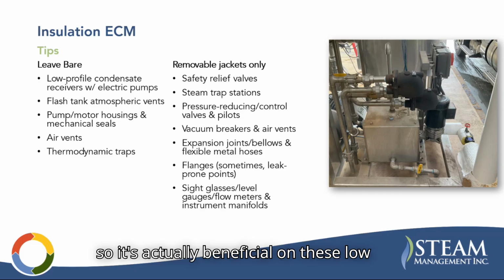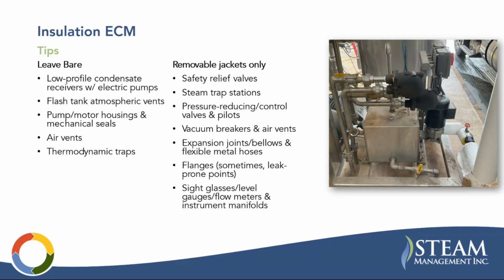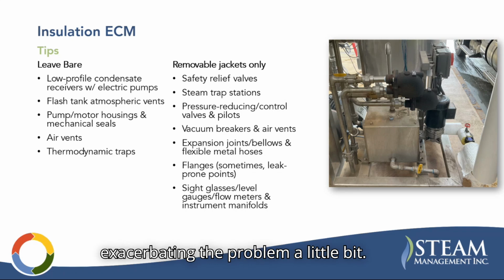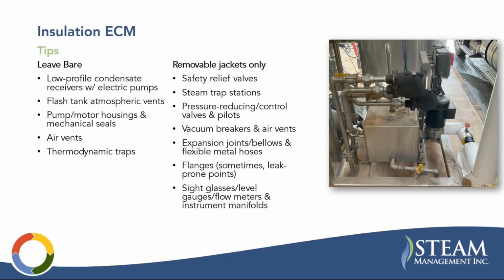And so it's actually beneficial on these low profile tanks to leave them uninsulated, as by insulating them, you're kind of exacerbating the problem a little bit. The closer it is to boiling, the easier it is for that pump to cause the water to boil and cavitate. So anyway, that's the idea. So this is something that if there is enough head on the tank, if it's a tall tank and kind of a high operating point on the liquid level, then maybe it's okay. But a lot of times you want to leave those uninsulated.